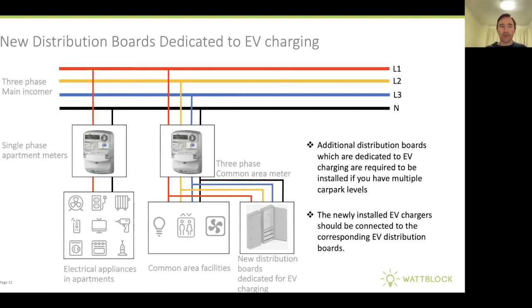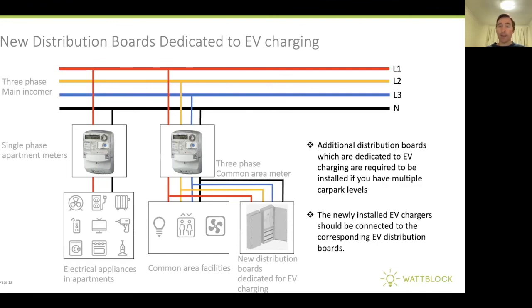Sometimes you need new distribution boards dedicated to EV charging. You can see line one, line two, line three, and neutral or earth. Here's an example of a single phase apartment meter coming off one of the three phases — in this case L1 — and a three phase common area meter coming off L1, L2, and L3. New distribution boards dedicated to EV charging can be spawned off the common area circuits out of the common area meter, and these can be installed in the car park area. Once the distribution boards are installed in the car park, the EV chargers can be connected to the corresponding EV distribution board.